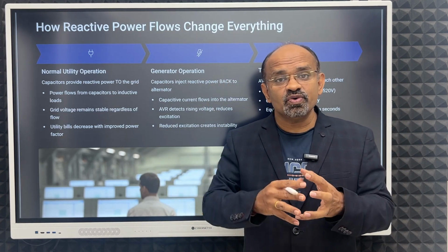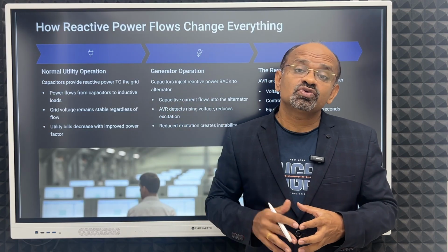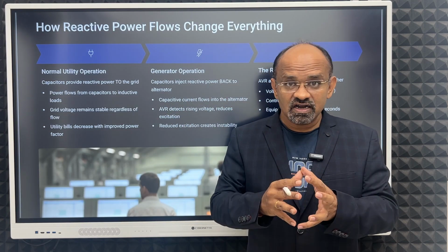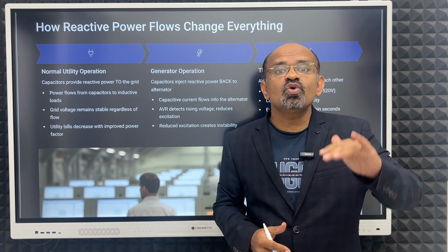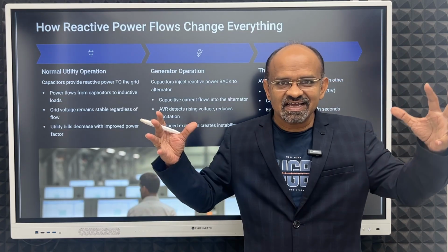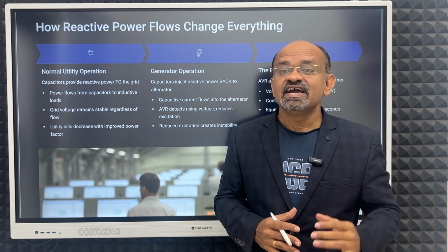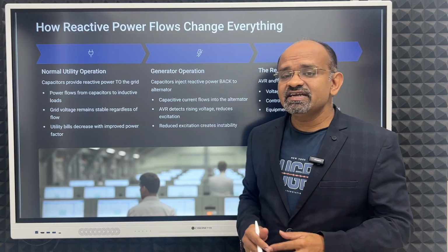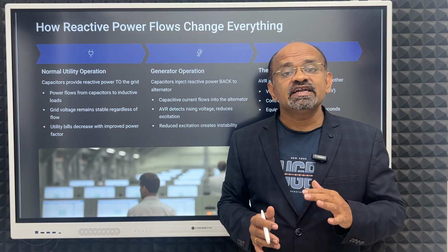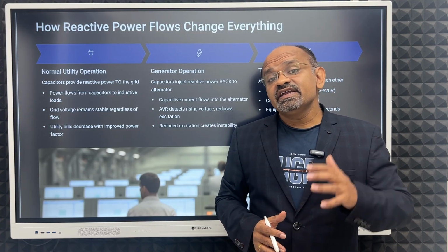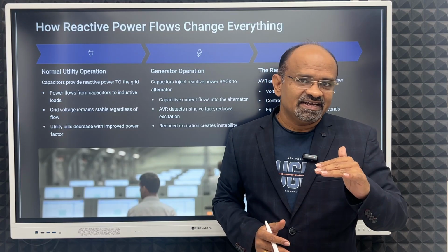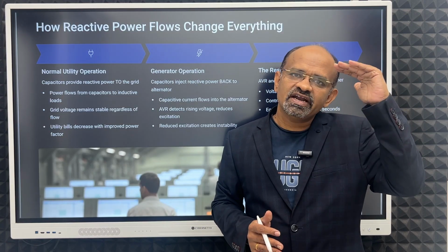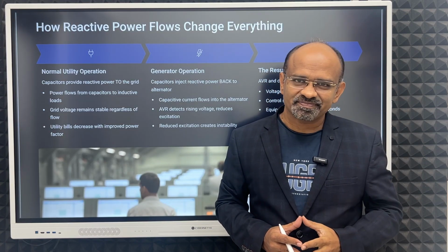We know from the earlier video at the start of this module that as excitation increases, voltage increases, and as excitation decreases, voltage decreases. So the AVR detects a rise in voltage and decreases the excitation. Now, ultimately, the entire voltage will go down.